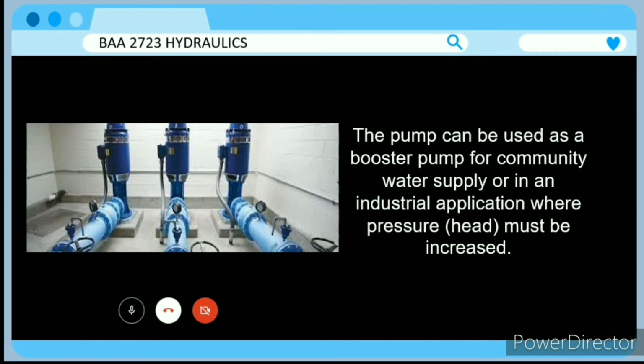Lastly, the pump can be used as a booster pump for community water supply or in an industrial application where pressure head must be increased. It could also take suction from a vacuum-sealed vessel, such as a hot well condensate pump. Vertical turbine pumps have flow rates ranging from 50 gallons per minute to 30,000 gallons per minute and higher, due to the pump being able to have one or more stages, and the amount of head it generates may be modified.